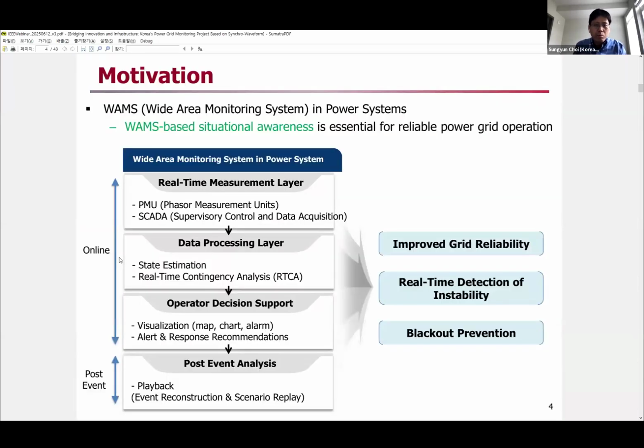Okay, so the wide area monitoring system, in short WAMS, in power systems. This WAMS keeps watching the voltage, currents, powers and reactive power in the wide area of the systems. Based on these measurements, it tries to provide situational awareness for reliable grid operations. WAMS first starts with real-time measurement, which is done by PMU and SCADA. PMU is phasor measurement unit, and SCADA is supervisory control and data acquisition system.